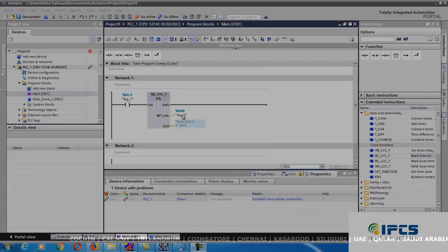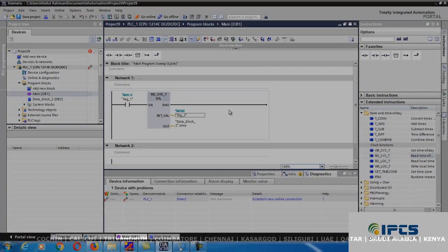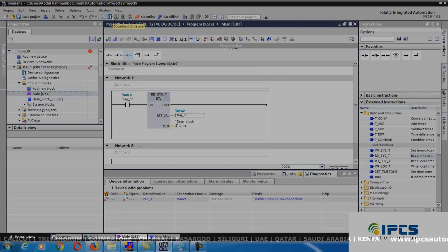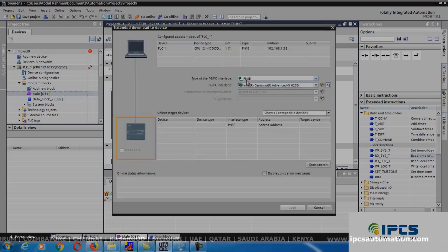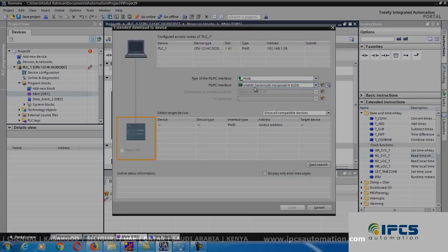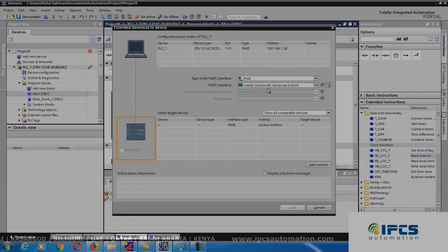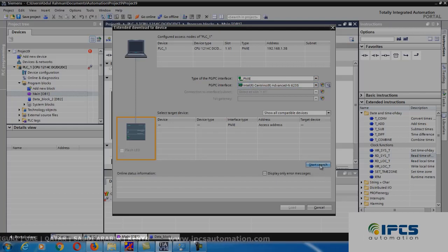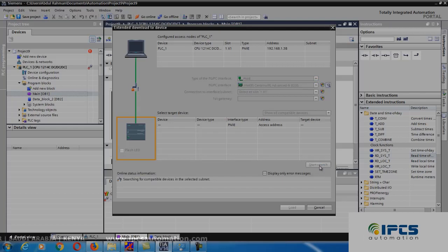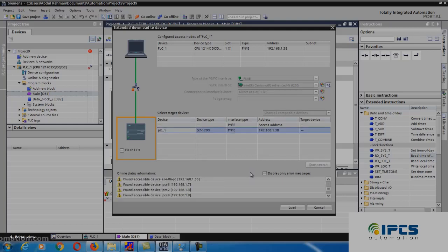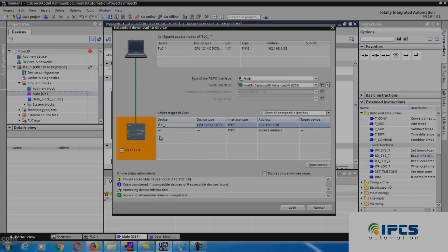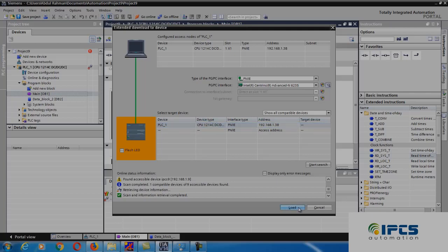To download the program, go to your main block and press this download to device button. In this, choose your PG interface and the motherboard name, and click start search. If your PLC is connected in that network, you will get an orange color over here and you can see the PLC here. Choose it and press load.